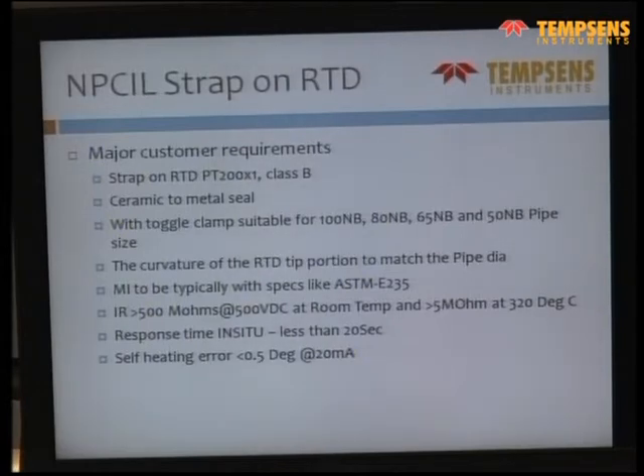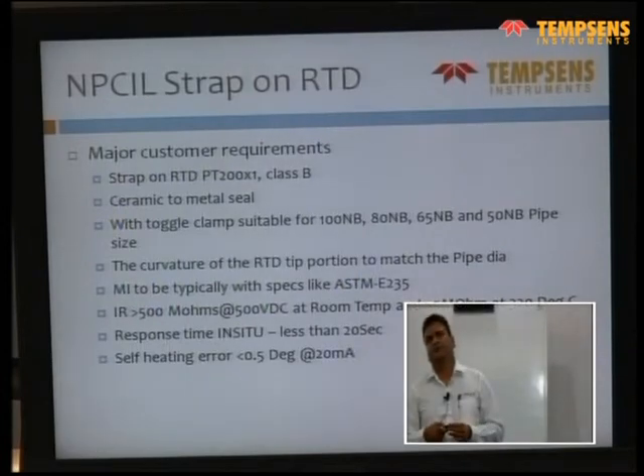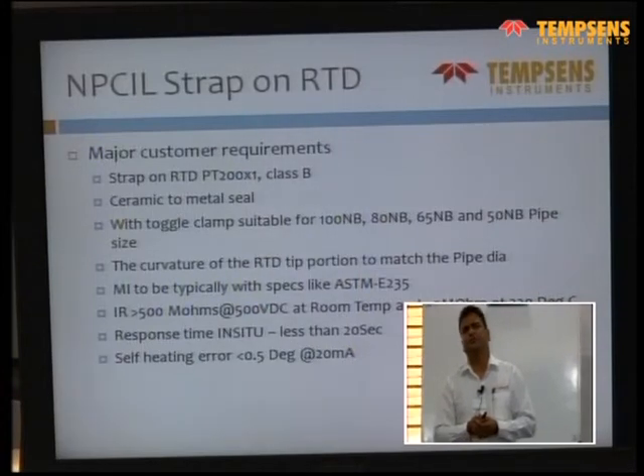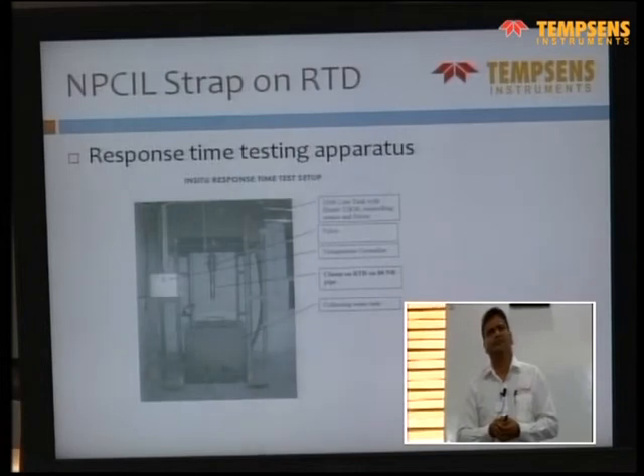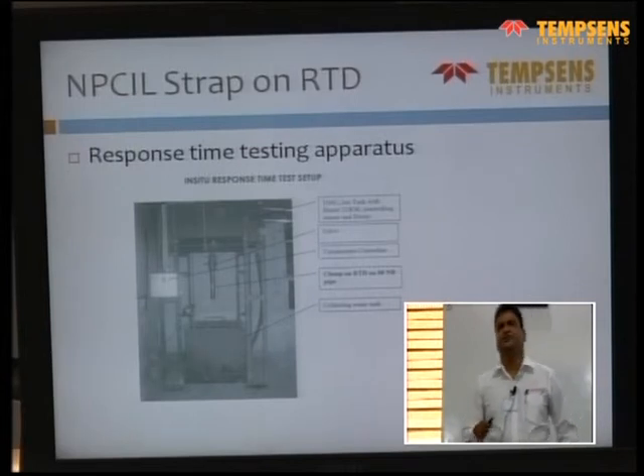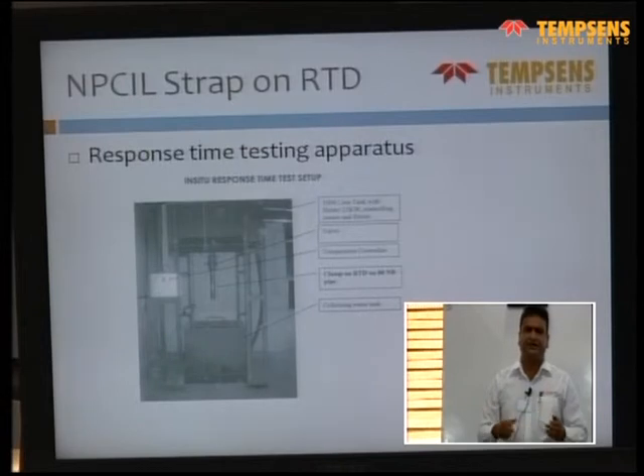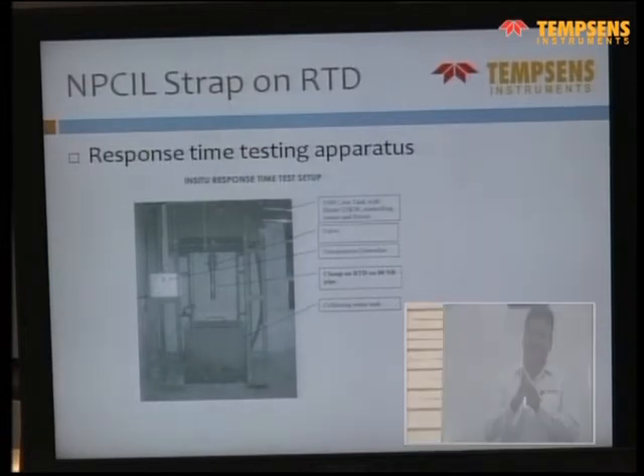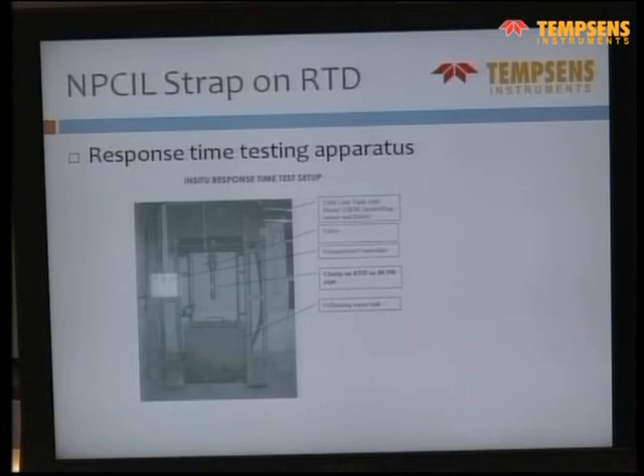Then you can also see tomorrow some strap-on RTDs for nuclear power plants. This is for taking the temperature outside the pipes in a nuclear power plant. Here the response time is less than 20 seconds including the pipe. So we made a special testing station in which, according to the pipe diameter, we supply the pad type RTD, skin RTD, with the clamp.